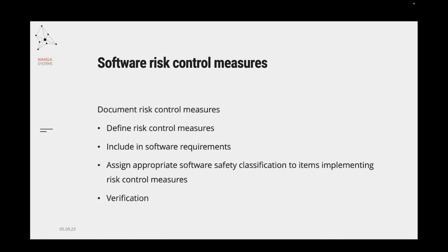And last but not least, software risk control measures. We have to document the risk control measures. We have to define them. We have to include them in software requirements, and assign appropriate software safety classification to items implementing risk control measures. And again, we have to verify the requirements that might be a result of risk control measures and the risk control measures themselves as well. And as I mentioned earlier, a great help for these can be a requirement or task management tool such as PTC Codebeamer or Windchill RV&S.